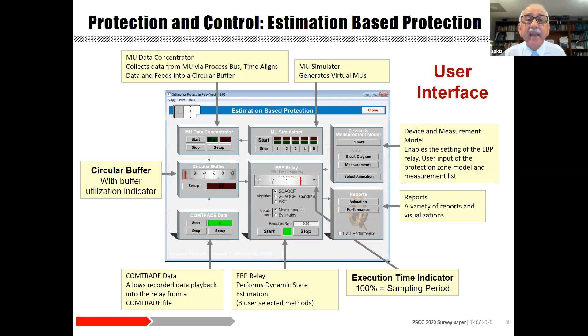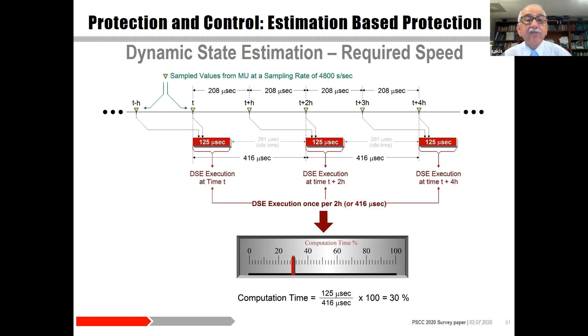And what I'm showing here is a particular operation of a protective relay of this sort. Notice that this dynamic state estimation is done every 416 microseconds in this case, because we're using sample values and so on, of course. And the computations, the analytics of the relay, take about 125 microseconds. So it can be done within the time frame that we have in order to do the analytics and go to the next set of data as they're streaming into the relay.